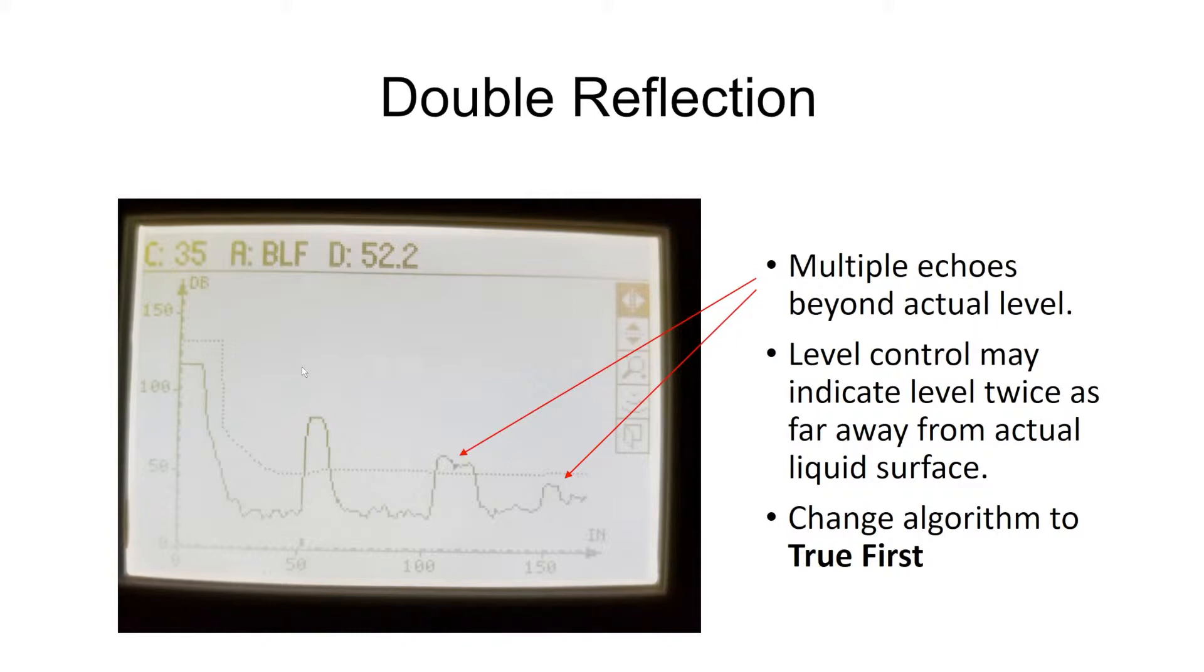Taking a look at this application, we have a very strong first echo. Then we have a second echo, which is not quite as strong, and a third echo. Looking at this, you can tell that the second and third echo are exactly two and three times the distance from the first echo. So, what do we do to get rid of this? The easiest thing we can do, and it works out most of the time, is changing the algorithm in the program from best of largest and first to a true first. What the level control will do in this case is choose the first echo that it sees above that TVT line and pick that as our level and ignore the second and third echoes.